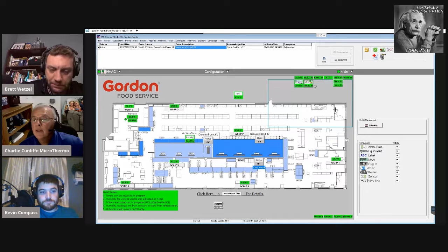There's one thing I want to show you which is pretty cool, something we call an MPC. Let's see if we have one on this store. I'm going to open this up for you. This isn't really network related, but it allows you to take one of our standard boards and jailbreak it. You see the node type is a 508, so that has eight. All of our 500 boards have 8 universal inputs, and the number 8, 4, or 12 tells you the amount of relays on the board. Here's what's being input to the board: Universal 1, Universal 3, all of these are unconfigured. This looks like the refrigeration trailer out back, and we're simply taking the temperature.